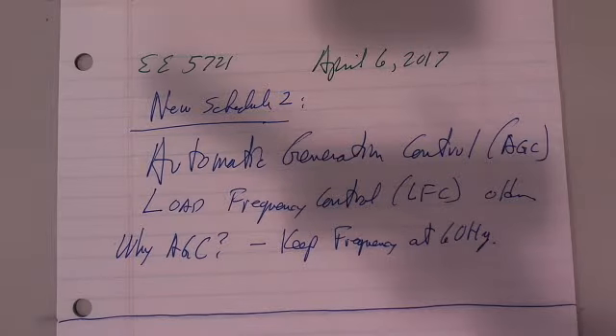Now, it used to be that they worried a very great deal about how close they were to 60, and they would integrate the error, which turns out to be how much time error a clock synchronized to the 60 hertz system accumulates. If you integrate the frequency error, you get the time error. And they have standards that want to keep the time error down to a certain small number of seconds or something like that per day.